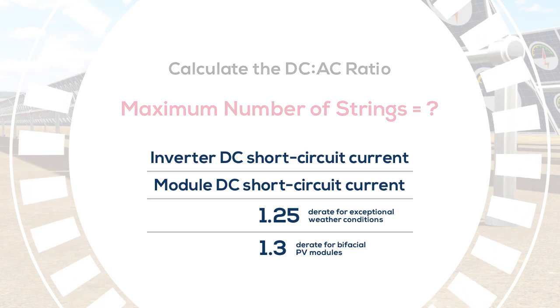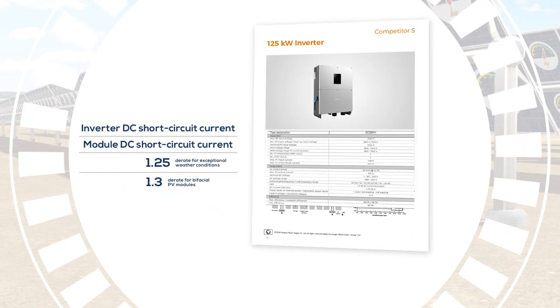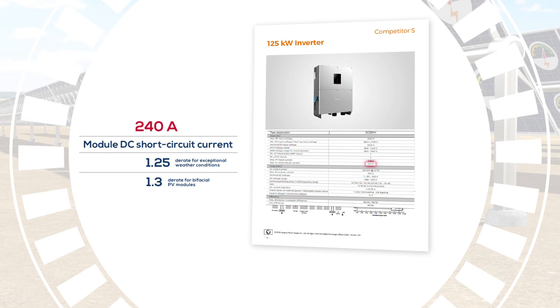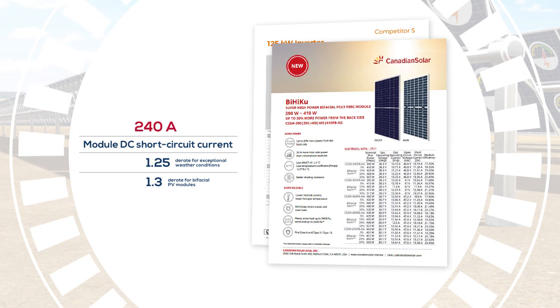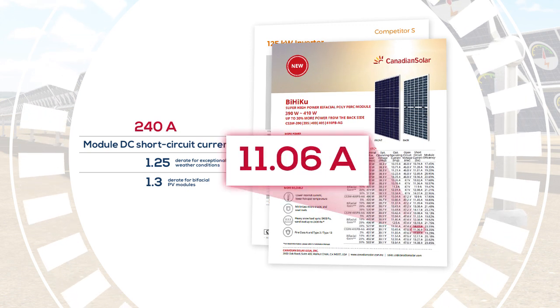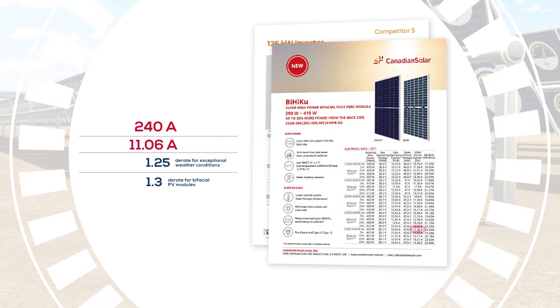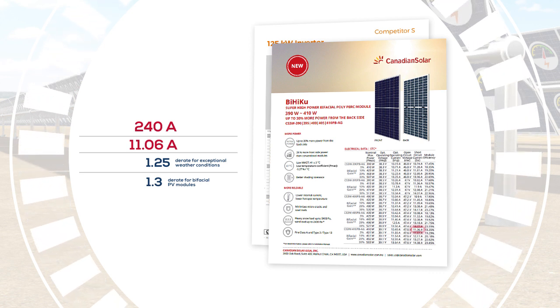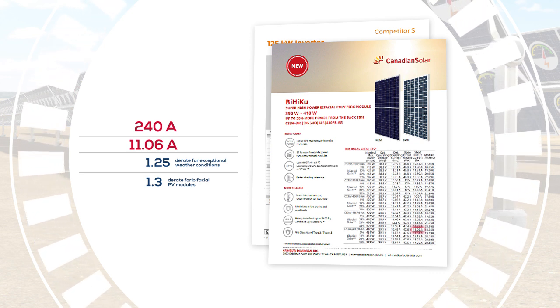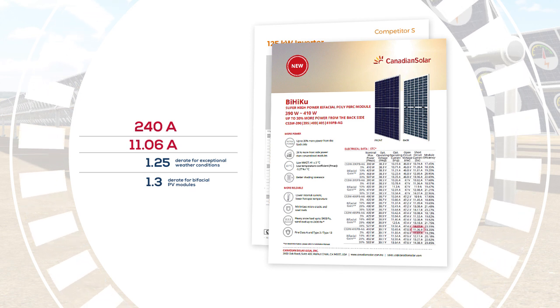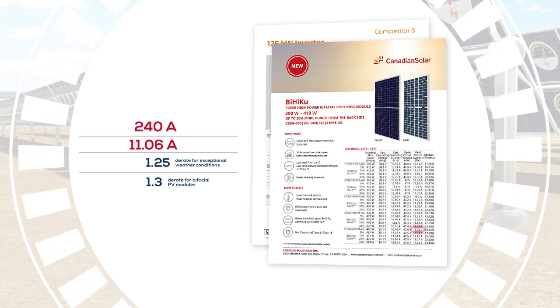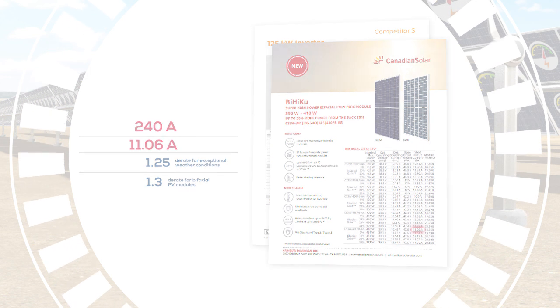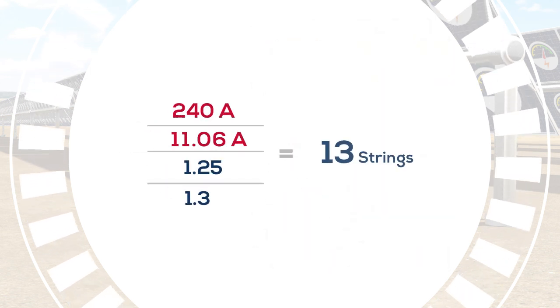With our competitor's 125-kilowatt inverter, the short circuit rating is 240 amps. The BiHiKu module delivers a short circuit current of 11.06 amps at standard test conditions. So the maximum number of strings is 240 divided by 11.06, divided by 1.25, divided by 1.3, which yields 13 strings maximum.